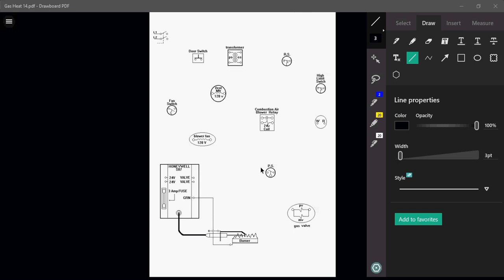Now, if that pressure switch does not close, that tells us that there is a problem. That problem could be a couple of different things. Obviously the inducer motor maybe didn't start like it's supposed to. Maybe the inducer blower wheel itself could be dirty. It could be a clogged flue pipe. It could be a cracked heat exchanger, just to name a few, that would cause that pressure switch to not close. It's a proving switch. It's a safety.